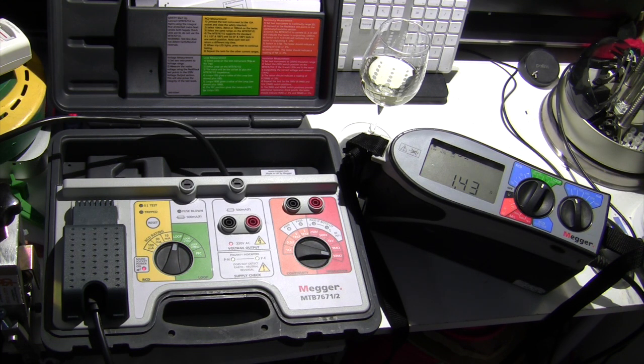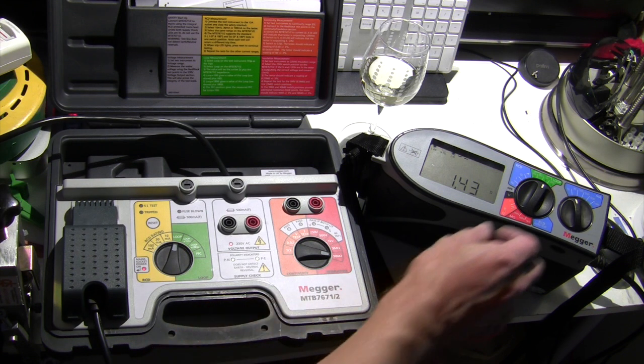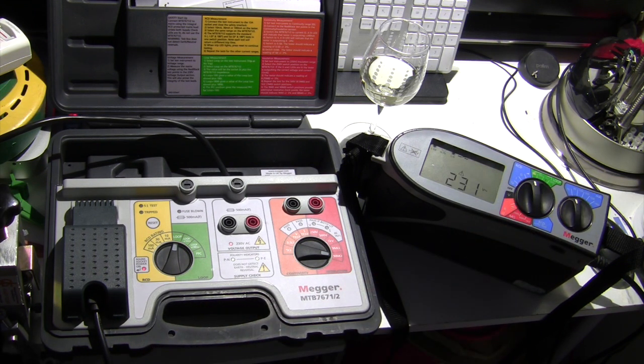I'm not too bothered about how high that number is, so long as when I plug the Fluke in under the same conditions I get the same sort of number. If both testers agree that that's the number on the end of this extension lead here, then that's fine by me. I can also perform that test of course on the no trip setting, where I should get the same sort of result. Certainly not too far off, hopefully, all things being equal. What was it, 1.43, and it's now, come on, 1.48. So a little bit of a discrepancy there, but not enough to keep me awake at night.